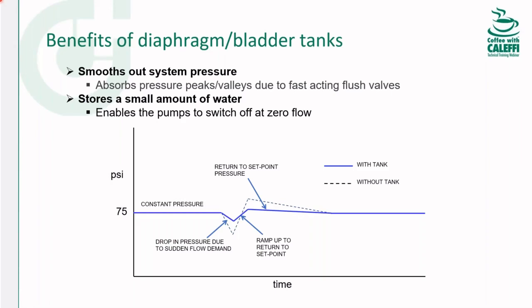So looking at this example, if you look at the dotted line, this is what happens when you don't have a tank. A large demand is going to quickly drop the system pressure, and the pump controller is going to see this drop, and it's going to ramp the pumps up as fast as possible to counteract the quickness of the pressure drop. So the problem is that since the pressure already dropped too much, the pumps are going to ramp up too much. They're going to overshoot the set point. And you controls guys out there could probably say, well, I could try and fiddle with the PID parameters, but in my estimation, it's just going to make it worse. So when you do have a tank, that would be the solid blue line. And basically under the same scenario, the tank is able to absorb some of that demand, and that gives the pumps time to ramp up and take over. So the drop and the corresponding overshoot are mitigated.